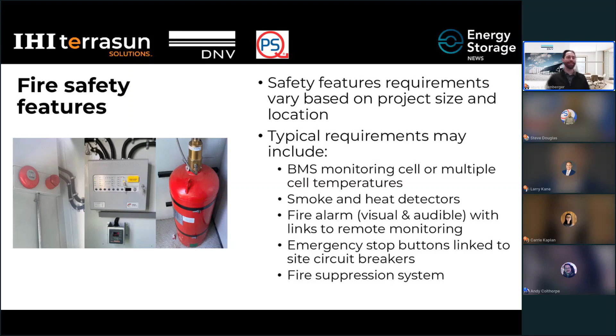Commonly, we see clean agent gases and aerosols being used as fire suppressants, and these are great for knocking down flames and putting out non-battery fires. The issue with lithium-ion battery fires is that thermal runaway can propagate through the cells, and it takes a lot of energy to remove heat from the cells to cool them to a level where thermal runaway will not propagate. Because of this, DNV really sees water-based systems, either sprinklers in the container or dry risers connected in an emergency situation, as the way to cool the batteries and remove a large amount of heat to prevent thermal runaway propagation.